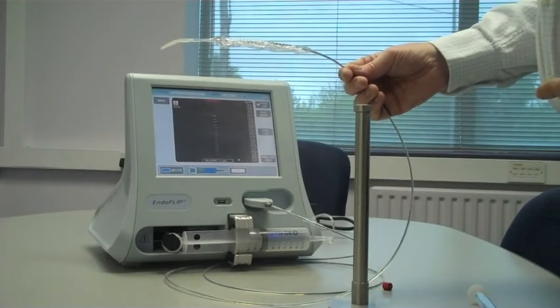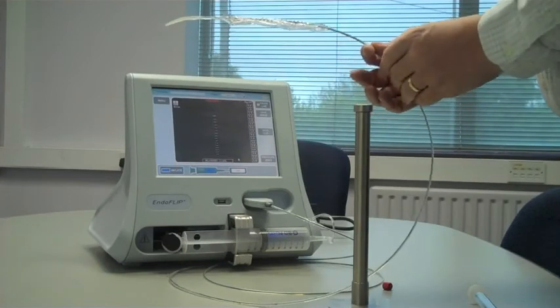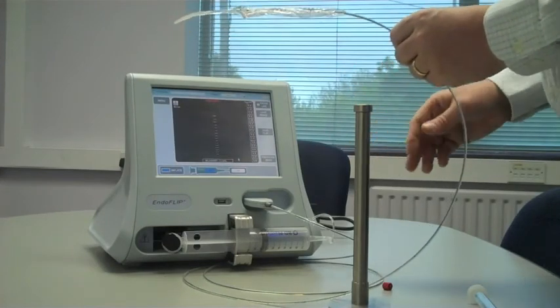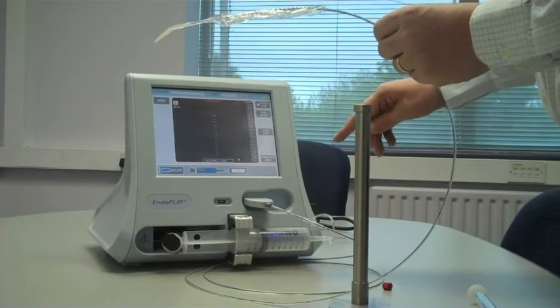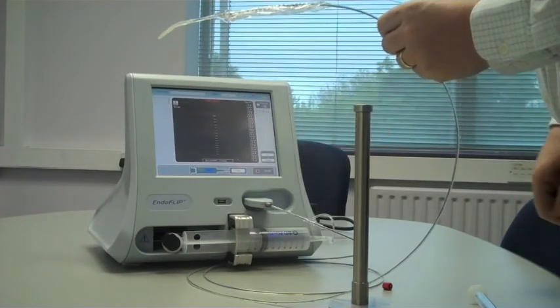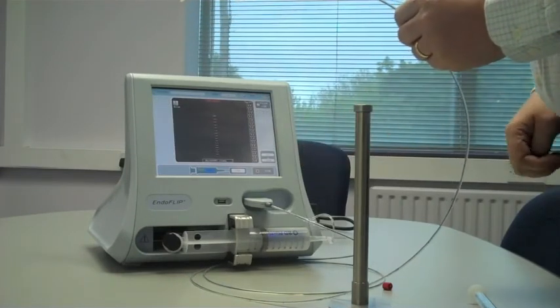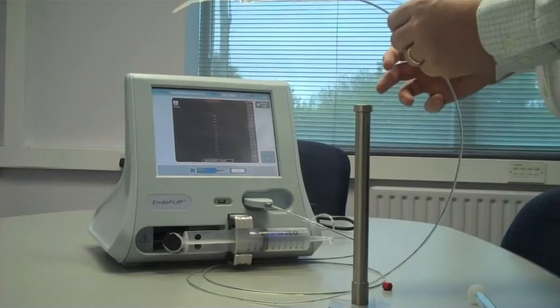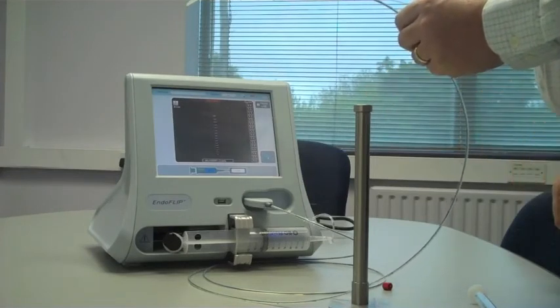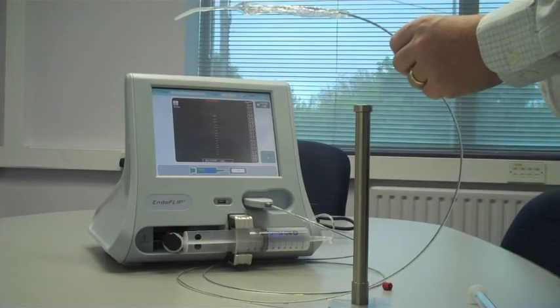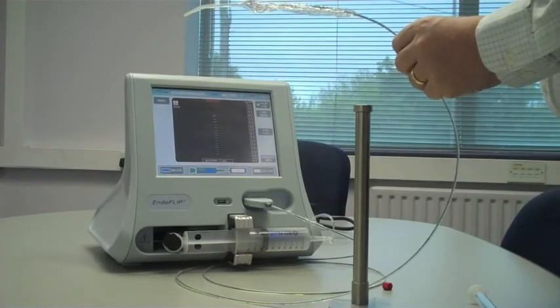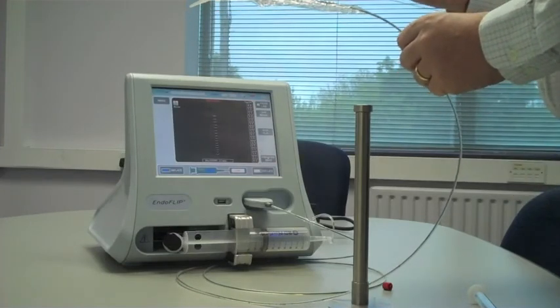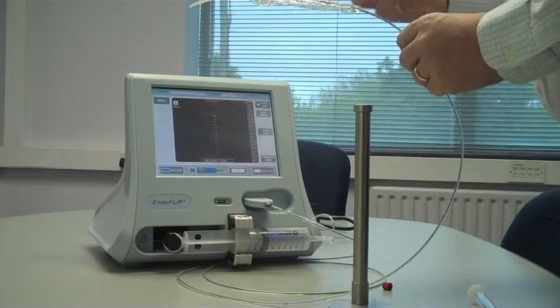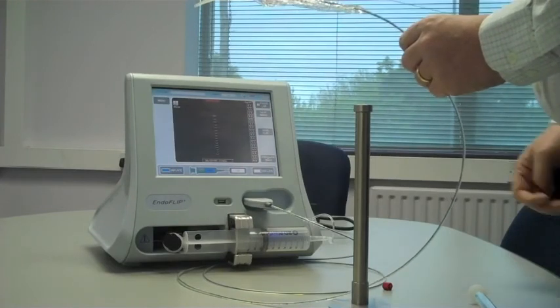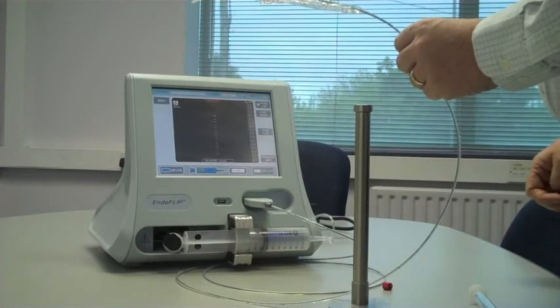Now that the machine is set up, a couple of points. I always zero the system right before placing the catheter into the patient, so you can hit pressure 0 should you wish, and it will inflate 1 to 2 milliliters into the balloon as part of that process. Always hold the catheter horizontal if you're doing a pressure 0, just so that you don't have the weight of the saline bearing down on the pressure sensor.